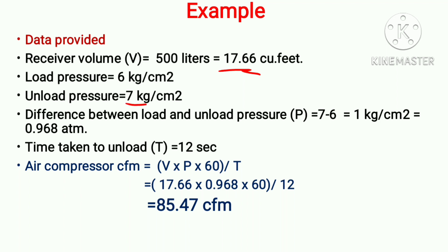The compressor loads at 6 kg and unloads at 7 kg. The difference between load and unload pressure is 7 minus 6, which equals 1 kg per square centimeter. We convert this pressure difference to atmospheric pressure: 1 kg/cm² equals 0.968 atmospheres. The time taken to load to unload is 12 seconds.